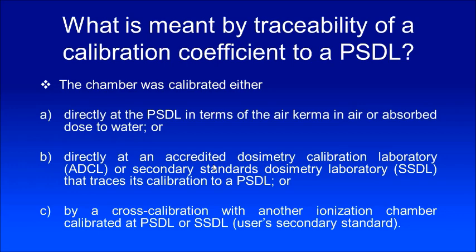When you measure output in your linear accelerator with your ion chamber, we say the ion chamber calibration should be traceable — we use this terminology 'traceability.' If you measure one gray for a certain amount of radiation, the same amount of radiation should produce one gray anywhere in the world. So there has to be traceability. When you say your measurement is traceable, that means the chamber you use is calibrated either in a primary standard laboratory directly for absorbed dose, or at an accredited dosimetry laboratory or secondary standard dosimetry laboratory which has a calibration with the primary standard.